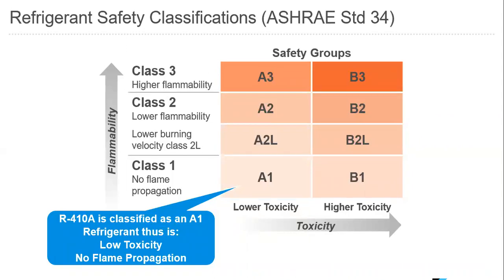Those safety groups are defined as A, which are lower toxicity safety groups, and then B, which are higher toxicity safety groups. And then we elevate these different safety groups. We go from A1 and B1 up to A3 and B3, depending on their flammability. So A groups are lower in toxicity, B groups are higher toxicity. R410A actually is classified as an A1 refrigerant. Thus, it has low toxicity and no flame propagation.